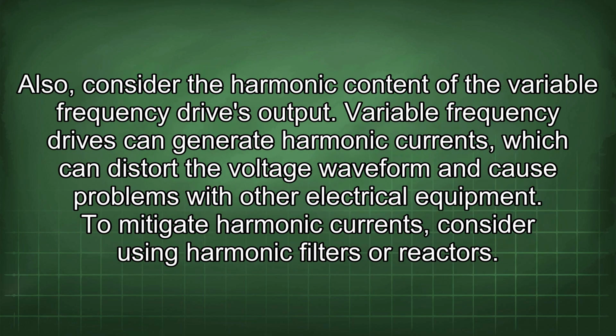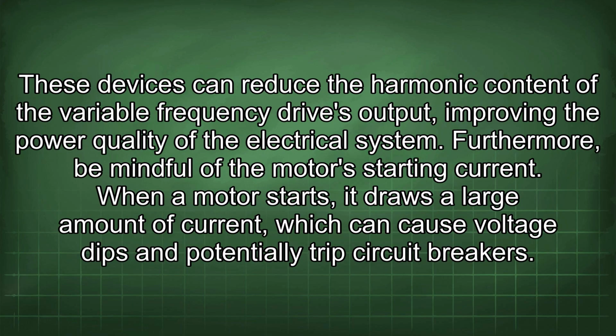Also, consider the harmonic content of the variable frequency drive's output. Variable frequency drives can generate harmonic currents which can distort the voltage waveform and cause problems with other electrical equipment. To mitigate harmonic currents, consider using harmonic filters or reactors. These devices can reduce the harmonic content of the variable frequency drive's output, improving the power quality of the electrical system.